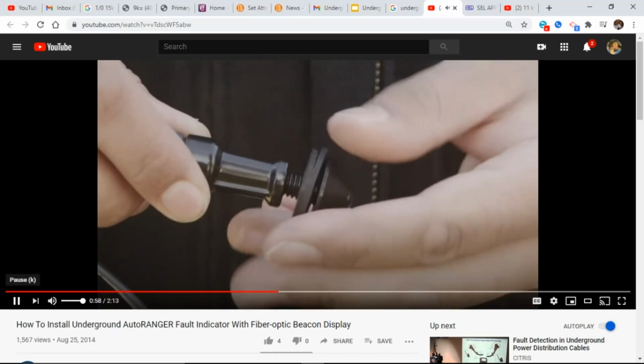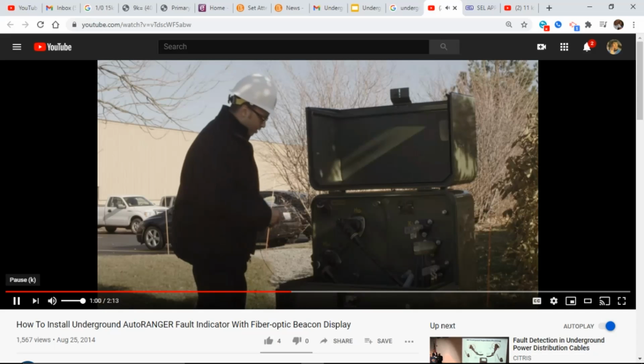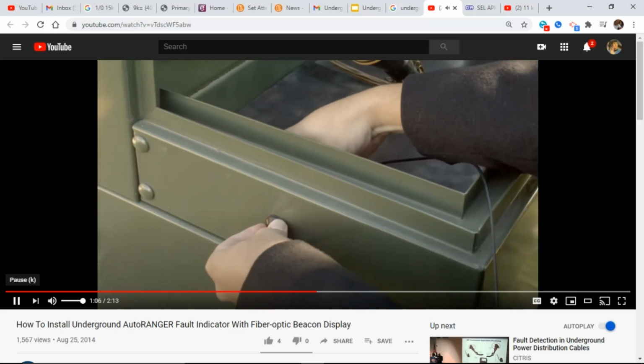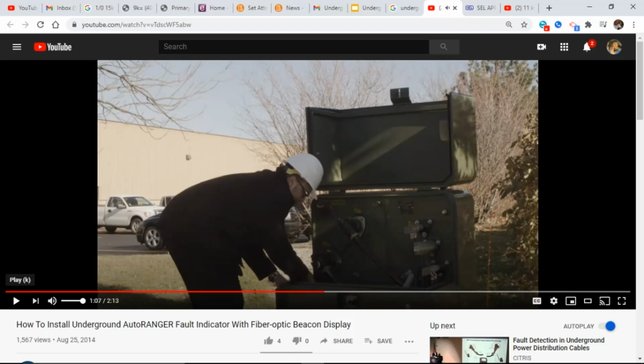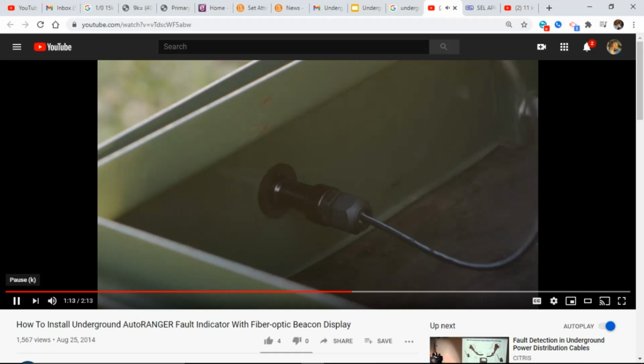Then you'll disassemble the display, insert it into the hole, and then reassemble the display head. I don't really quite get why they do this. Every indicator that we put on a transformer, we put on the front of it. Yeah. That's 2 that we've seen on the side. If you're driving down the street and you want to sit in your pickup and it's 29 degrees outside and snowing and raining or whatever, it sure is nice to just drive by it. Yeah. It's important that when you're doing this, that your equipment is de-energized, because you do have to reach inside of the enclosure to install it.